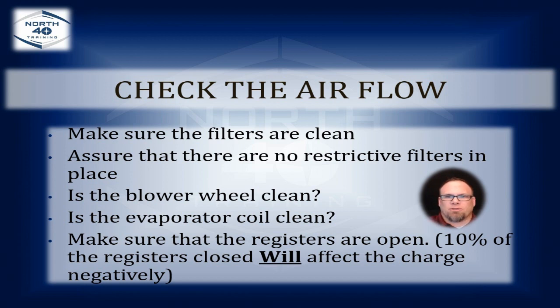Are the registers open? Now think about that. If you're only closing 10%, the average home has somewhere around 25 to 30 registers. That's three registers in a home that are closed. Probably most of the homes that you go in will have registers closed in them. It doesn't take much to create a negative effect in closing those registers. If you're not able to move that air down those runs, that does impact everything else. Now think about it.